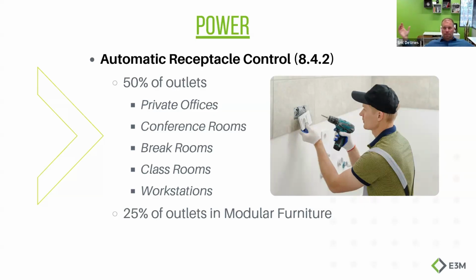Let's use my office as an example. Say I have 6 outlets in this office. 3 of those outlets need to be tied to my lighting occupancy sensor. So when I leave the room, if my AirPods are charging, if I have a fan running, or an Amazon speaker running, those things are supposed to shut off with the occupancy control. Obviously you still have constant live outlets to run things like your computer and printers.